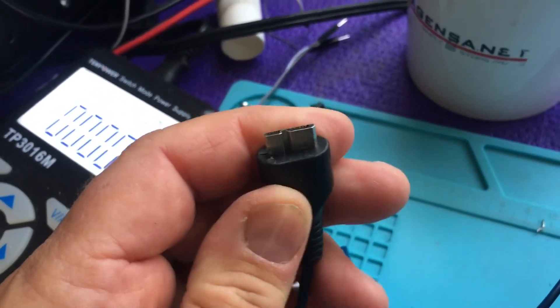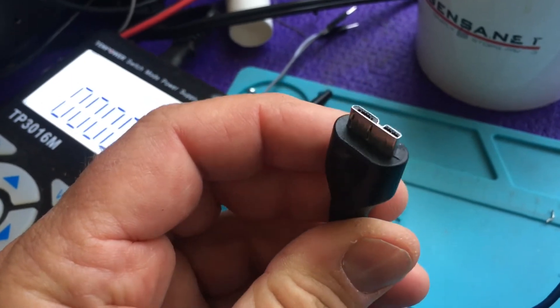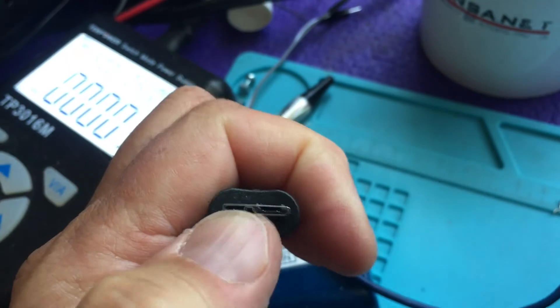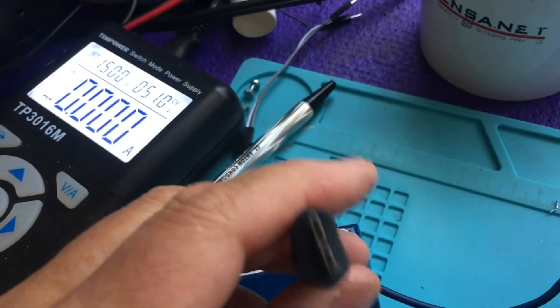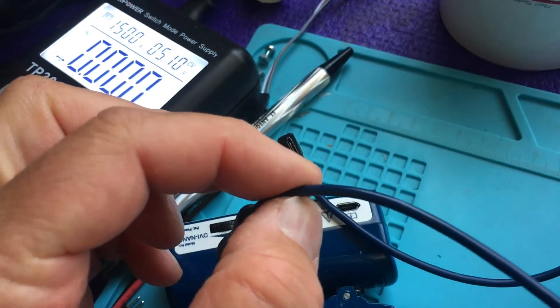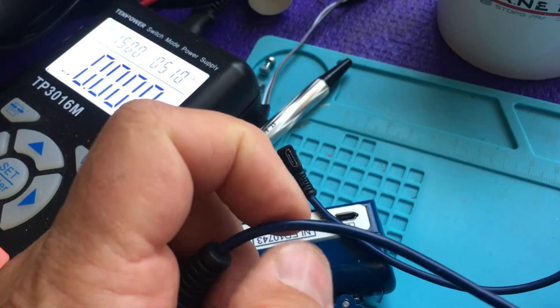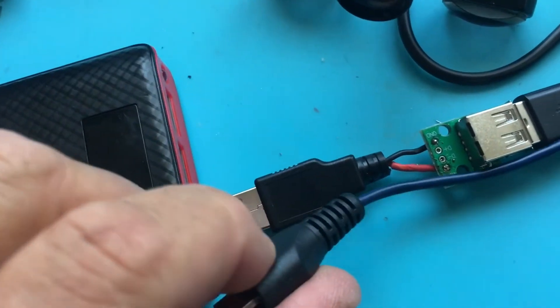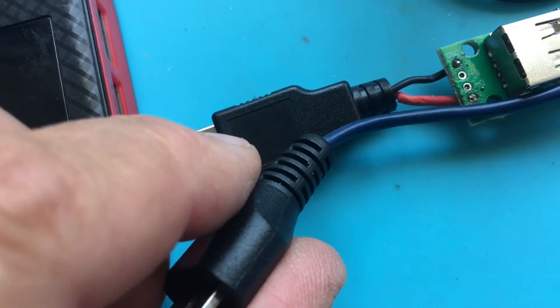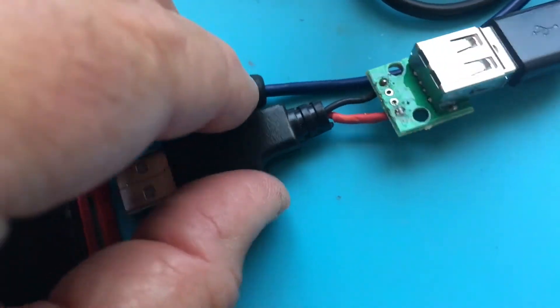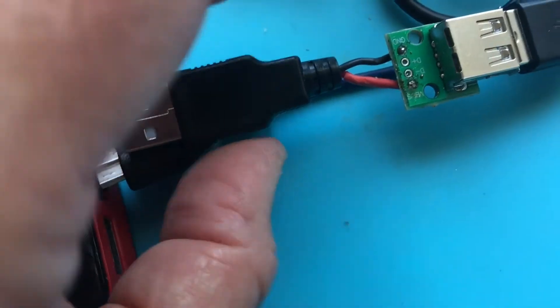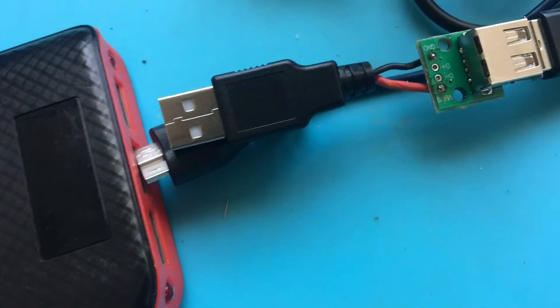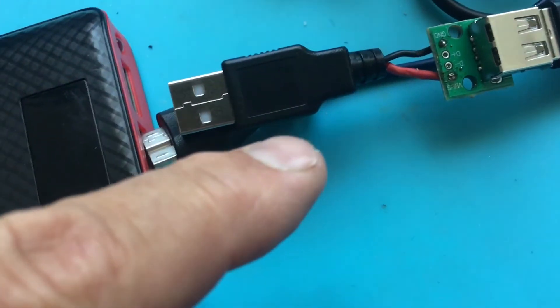So what would happen if you had one of these fail and you needed to come up with something quickly? These aren't readily available, the configuration here. And the pin out here is unknown. So I haven't checked that out, but it would be possible to sever this end here and then put on one of these cable ends. Then we could just have our - it would kind of look like this without the crossover. We could just run our own, we could make our own cable that would hook to a power pack. And it would just require two connections. And you just have to make the connections right like I did here.